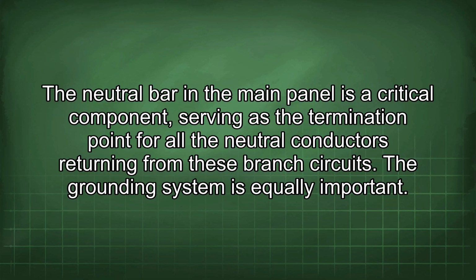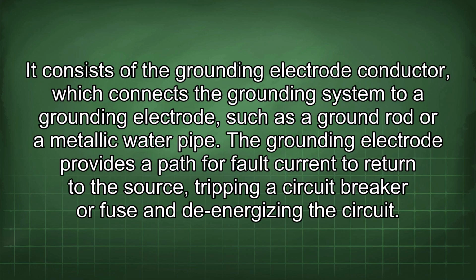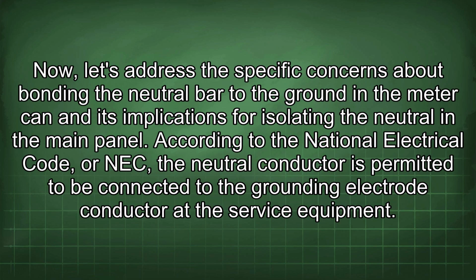The grounding system is equally important. It consists of the grounding electrode conductor, which connects the grounding system to a grounding electrode, such as a ground rod or a metallic water pipe. The grounding electrode provides a path for fault current to return to the source, tripping a circuit breaker or fuse and de-energizing the circuit. Now, let's address the specific concerns about bonding the neutral bar to the ground in the meter can and its implications for isolating the neutral in the main panel.